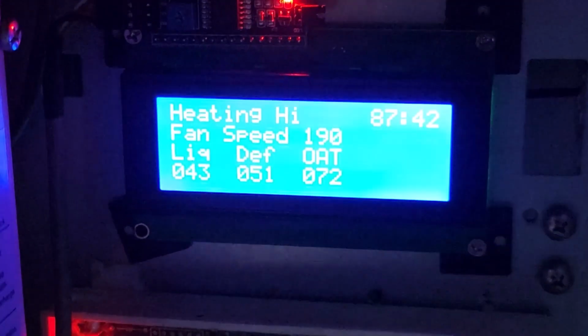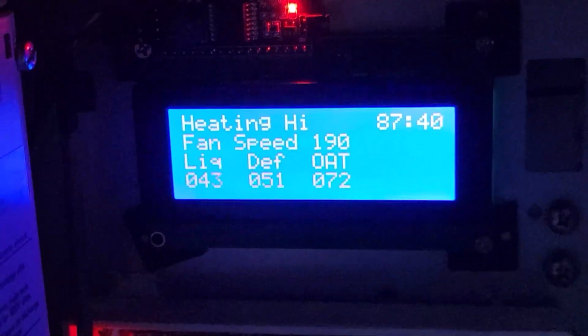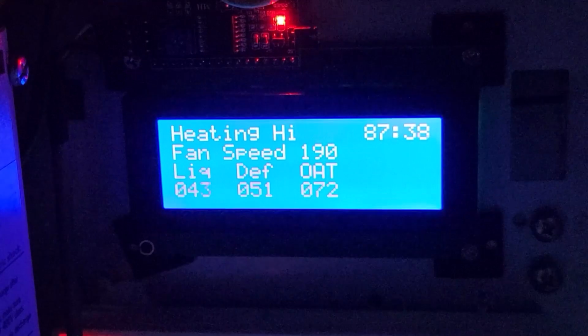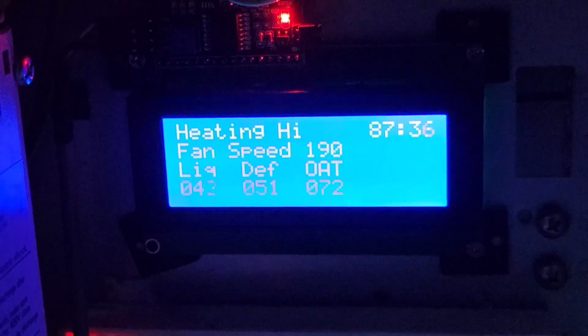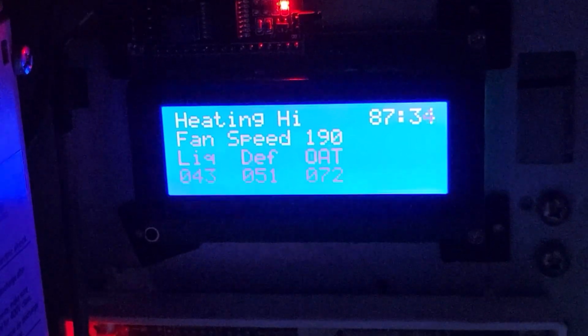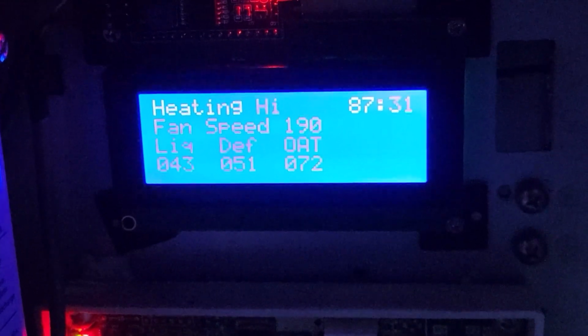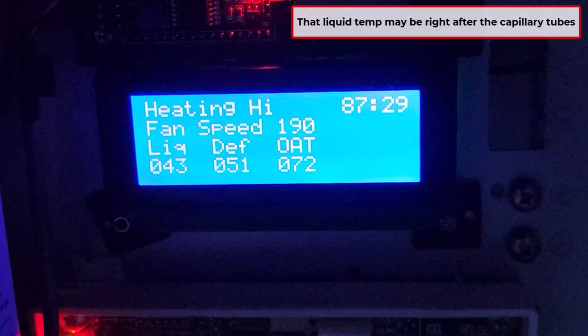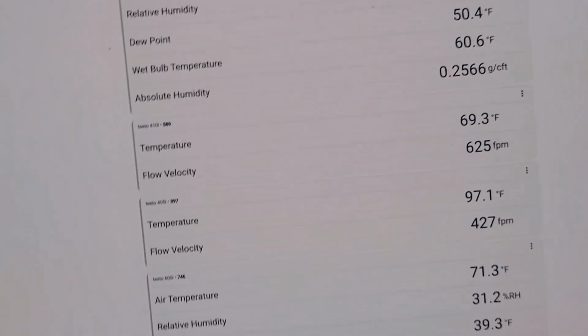Kind of thing, look at these. Oh, you can see the liquid line temperature right there. So that defrost sensor is in the coil, about 51 degrees, but the liquid line temperature isn't in the same spot as liquid would be for cooling, but it's reading for design. Outside air temperature 72, is that actually pretty close? It is pretty close, so that's just a little thermistor hanging in the original sensor back there.